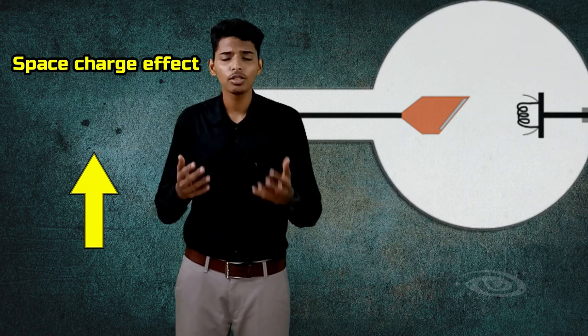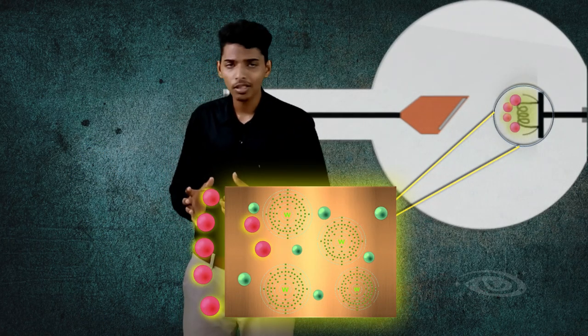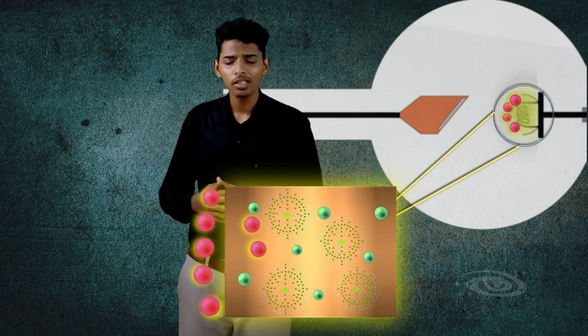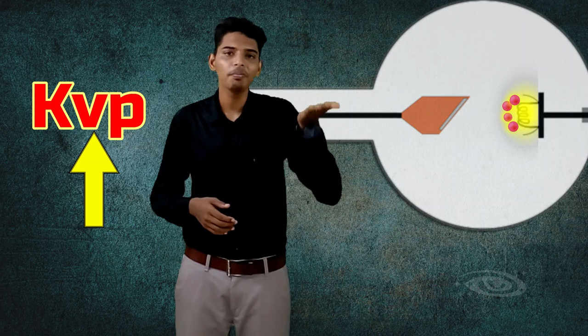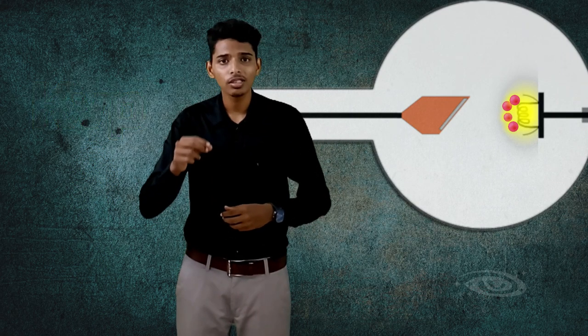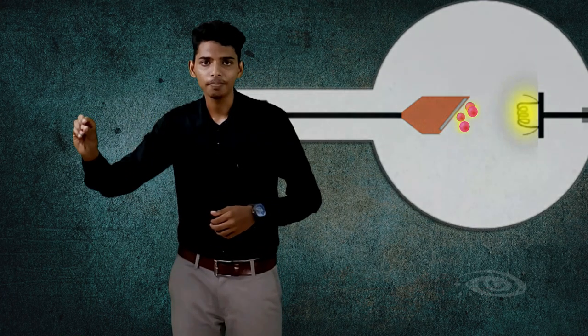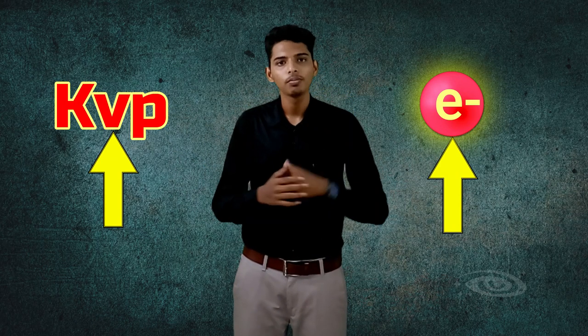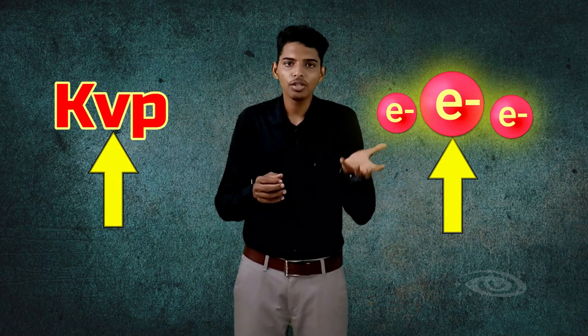There is a problem when you increase the tube current: the space charge effect occurs, where electrons form a cloud near the filament, causing electrons arriving behind to be repelled back into the metal. To overcome this problem, we increase the tube potential — that is, kVp. If we increase kVp, the electrons gain sufficient energy and move at high velocity. Keep in mind that increasing kVp increases the energy — that is, the velocity — of the electrons.